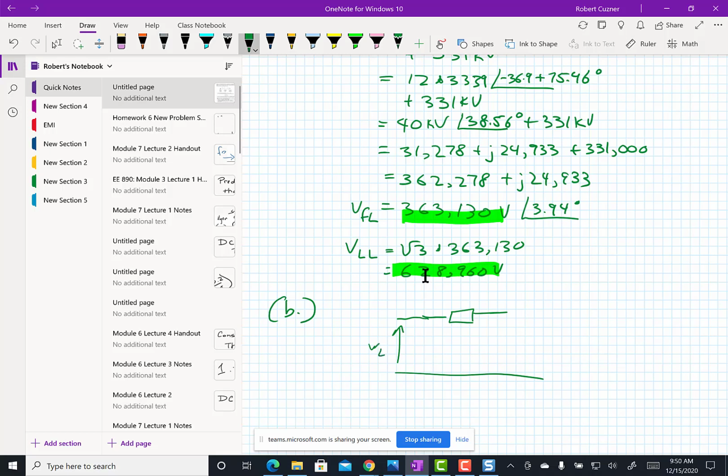This is what the guy at the power plant is going to program his regulator to run at to get the voltage he needs at the load end. And there's the ZT2, but with a prime because it's moved to the 4160 volt side.